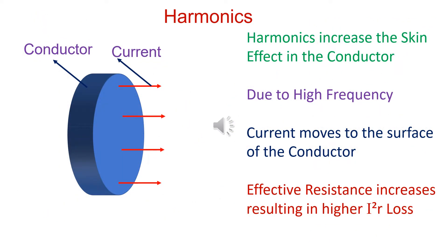Harmonics have a number of disadvantages. An example is skin effect. At high frequency, current flows from the skin of the conductor. Effective area of the conductor decreases. This results in increase in effective resistance, resulting in higher I squared R loss.